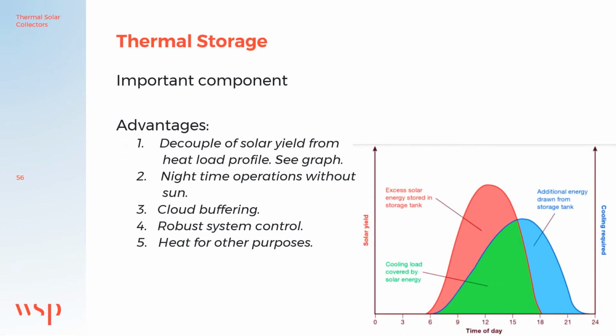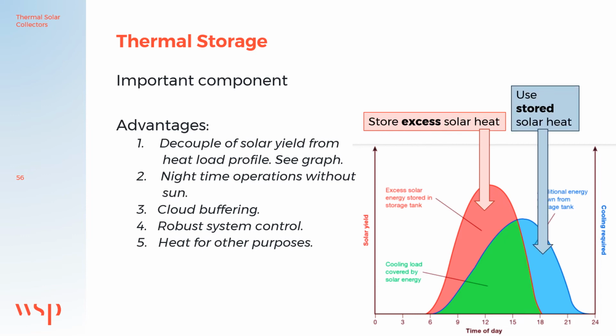Thermal storage of heating or cooling is a very important component of solar cooling systems. It is important to differentiate between heat storage and cool storage. Although storage is not generally necessary for overall system operation, it provides important advantages, which are: number one, decoupling of solar yield from the load profile during periods of high solar irradiation and low cool demand. 2. It allows nighttime operation without sun.